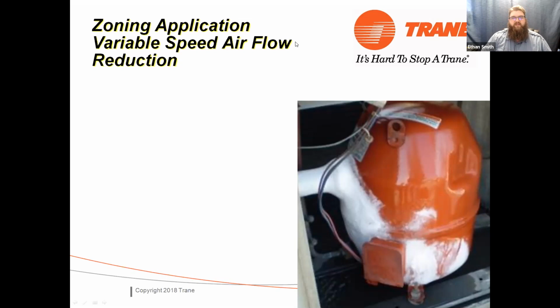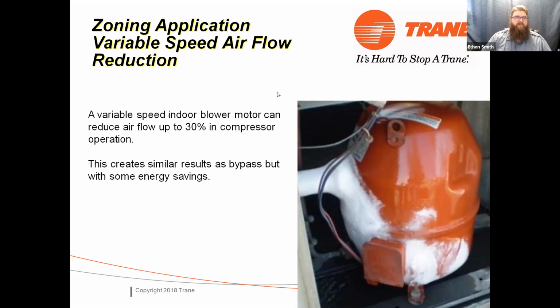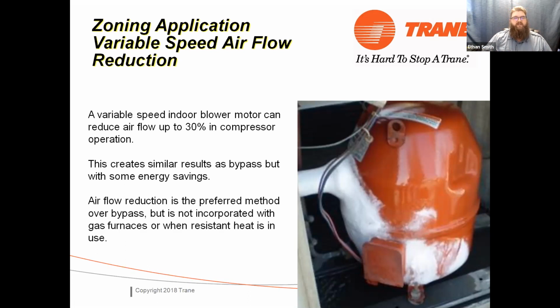And we're able to do this with an integrated zoning system. Okay. It creates a similar effect to bypass where we don't have an excess air problem anymore, but we can do it with some energy savings. Okay. The trick is you got to have that integrated blower with the zoning system.